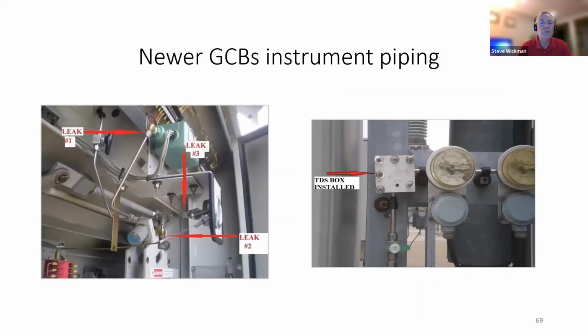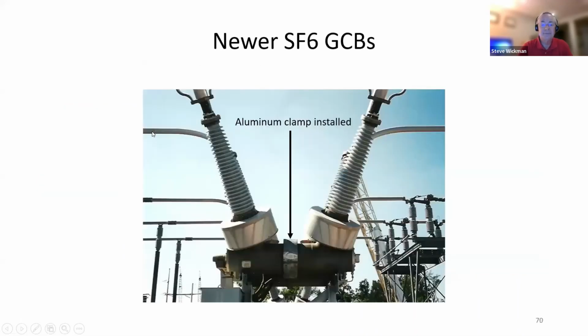Some of the newer lower voltage breakers have a lot of small instrument piping. We have built little box clamps, similar to what we would put around a radiator drain valve, to contain leaks where these fittings have a propensity to develop leaks. Dead tank style breaker with a flange going down the middle. We put clamps around those to contain those.